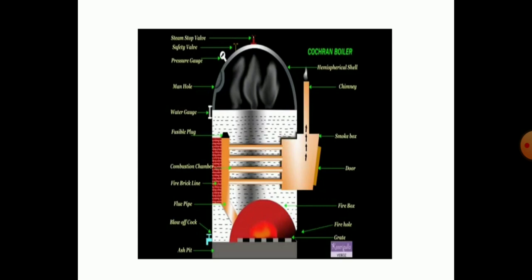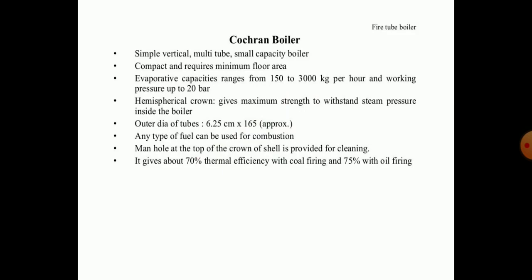In front of your screen, the pictorial view of a fire tube boiler is shown, depicting the parts, tubes, chimney locations, cross-sectional area, and at the top head the crown-shaped area containing high-pressure, high-temperature steam. The Cochran boiler is a vertical, multi-tube, small-capacity boiler which is compact and requires minimum floor area. It has an evaporative capacity ranging from 150 to 3000 kg per hour, while working pressure is up to 20 bar. The hemispherical crown gives maximum strength to withstand the steam pressure inside the boiler.